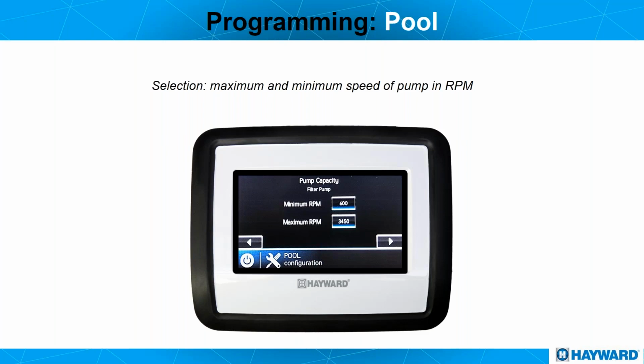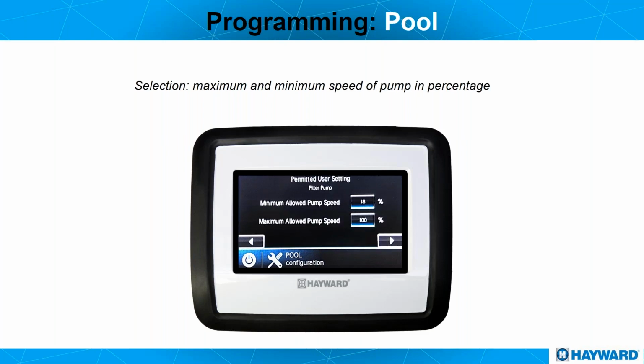You can adjust this, and later on when we have the controller up and running, we'll see that the maximum we're able to go to is what we set it for—in my example, it was 3,000. You can do the same with the minimum. Maybe you don't want it to go to 600; maybe you want it to go no lower than 1,000. You change it here, and in the future you won't be able to go below that unless you go back into the configuration and make changes.